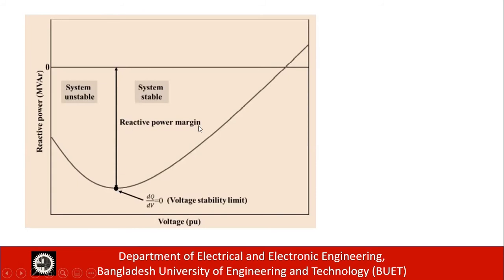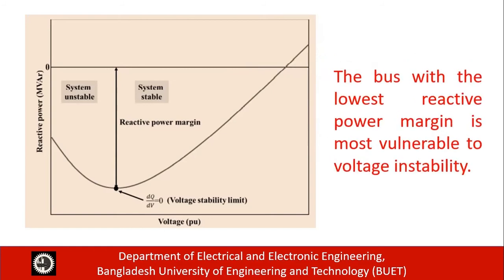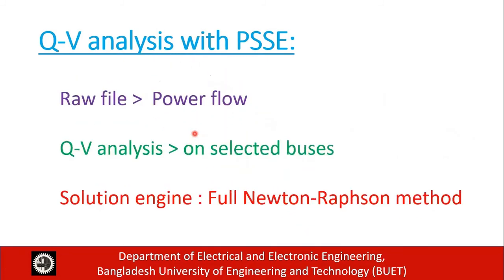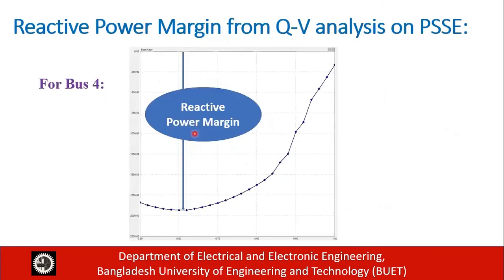The bus with the lowest reactive power margin is most vulnerable to voltage instability. For the QV analysis with the software, we took the raw file, did load flow analysis, then performed QV analysis on selected buses. We used the full Newton-Raphson method as the solution engine. After performing QV analysis, we obtained reactive power margin for all buses. For example, here is the QV curve for bus 4, where the difference between the base case operating point and the collapse point indicates the reactive power margin.